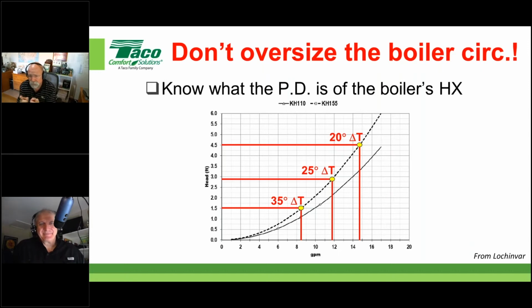I think the point John's making is, look, even if you have what's known as a higher pressure drop boiler heat exchanger, that's not a bad thing. You just have to design accordingly.